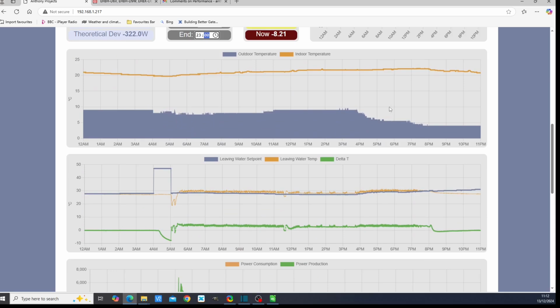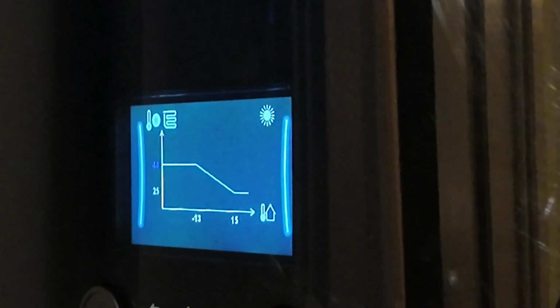When we have temperatures which are lower, we have flow temperature set points which are higher. And my experience is that if we have a flow temperature which is 30 degrees or higher, we're going to have an efficient use of the heat pump. So therefore, it stands to reason that what we need to do is set the minimum leaving water temperature to 30 degrees on the weather dependent curve. There is, however, a bit of a problem.